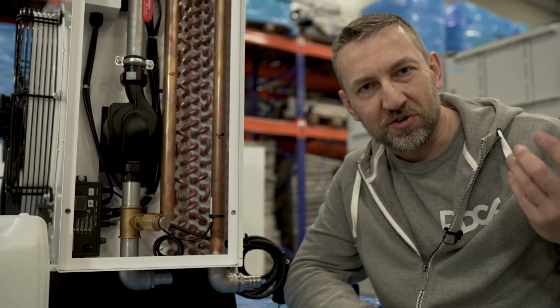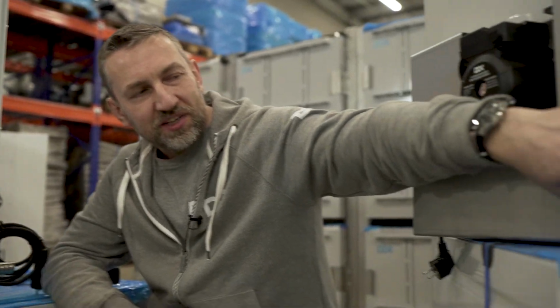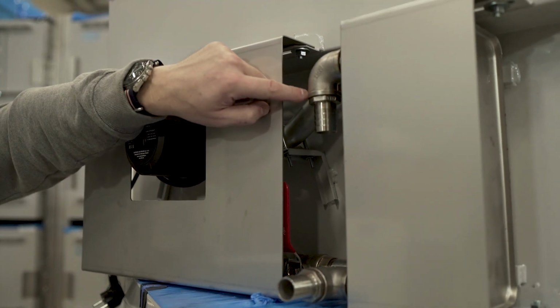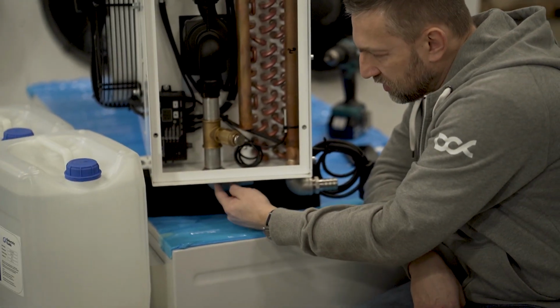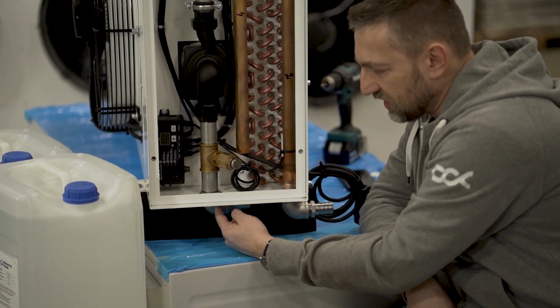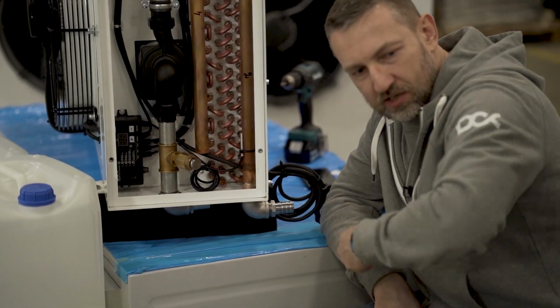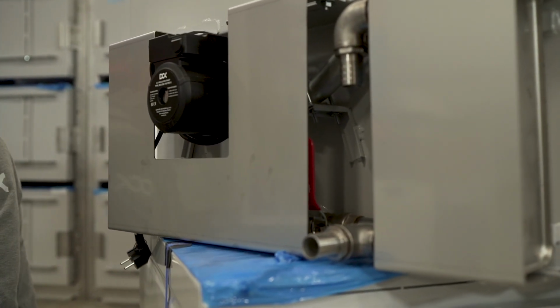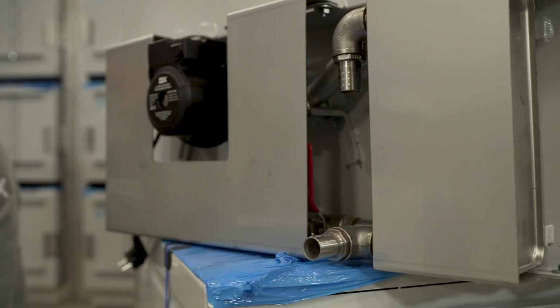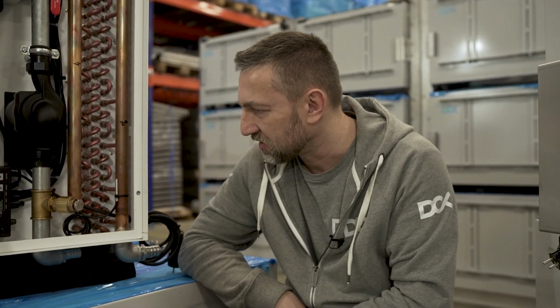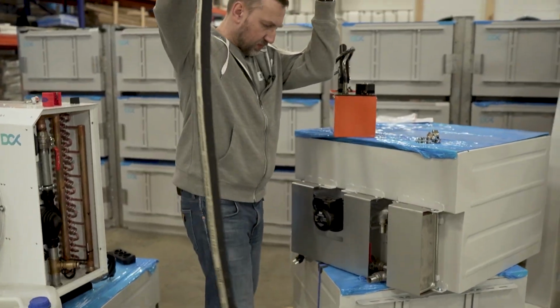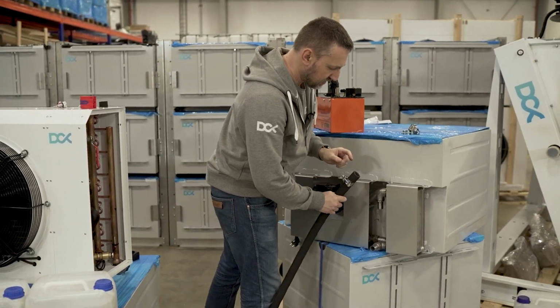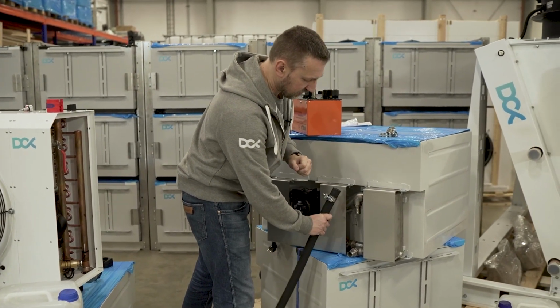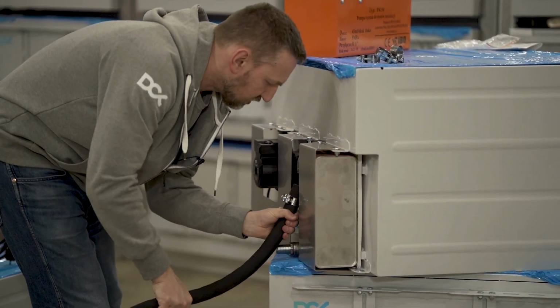And on the enclosure on the other side, the bottom one is the inlet and the top one is the outlet, right? So from the top here to the inlet, and from the dry cooler outlet to the inlet of the enclosure. Simple as that. And actually there are markings on the heat exchanger, so you can see how the flow through the exchanger goes, right? So let's connect both components.